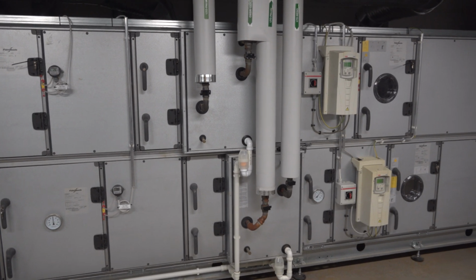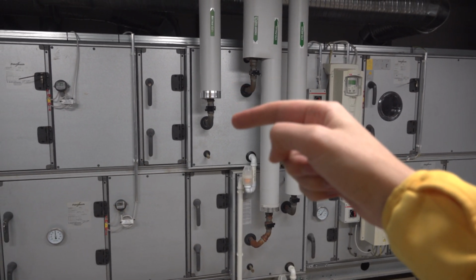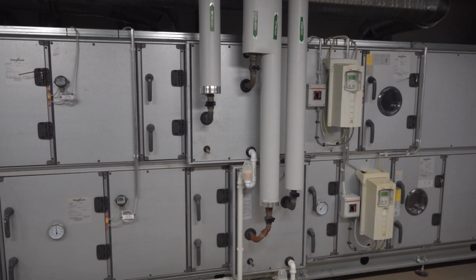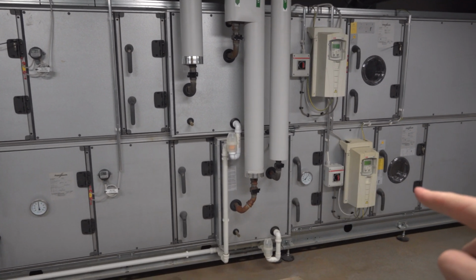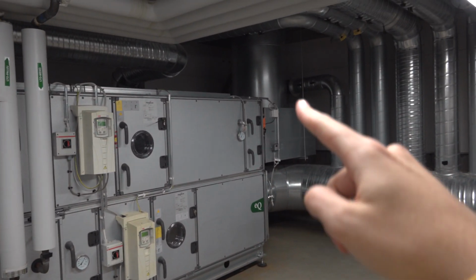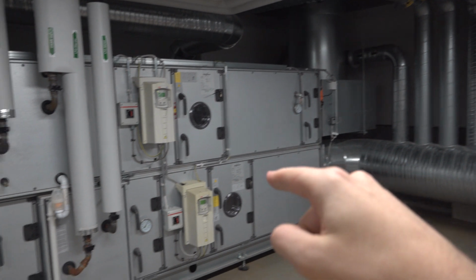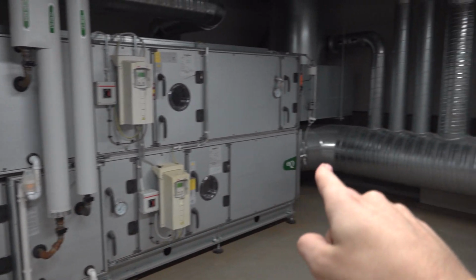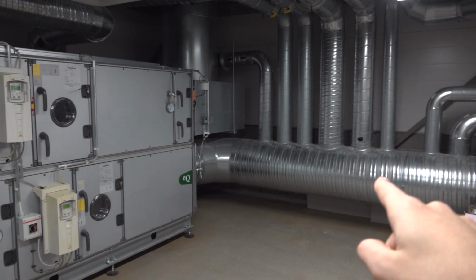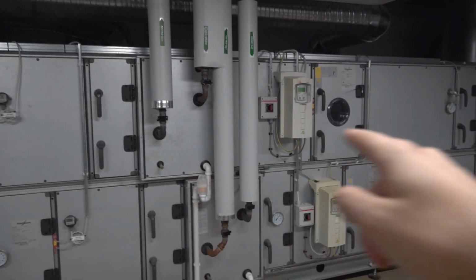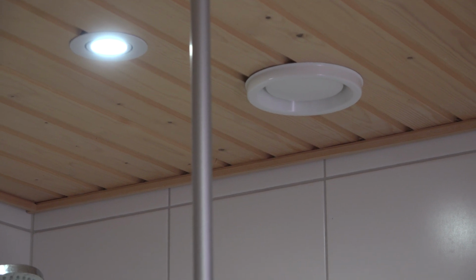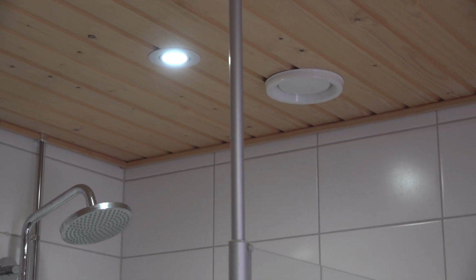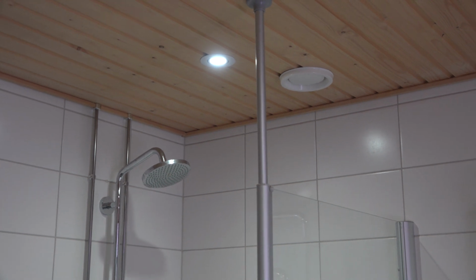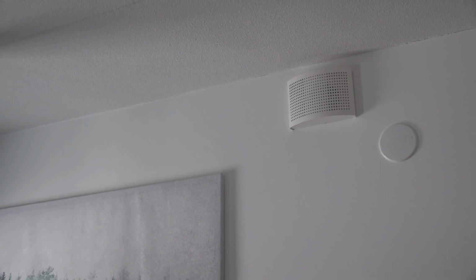So how this system works is that thermal energy is being gathered by this heat exchanger and being circulated back into the lower heat exchanger, which then heats the input air of the house. So air that goes into the ceiling is much colder, and the air that goes to the homes has been heated with the exhaust air. Here you can see an exhaust vent in our bathroom, which takes the air from the apartment and exhausts it out. And here you can see the air inlet in our bedroom, where the fresh air from the roof comes from.